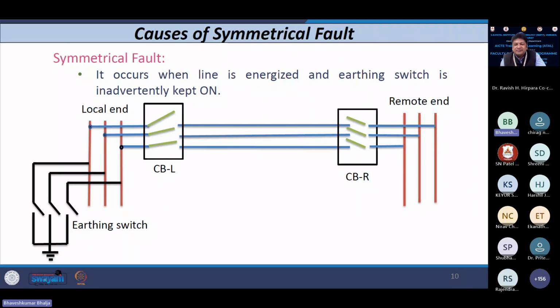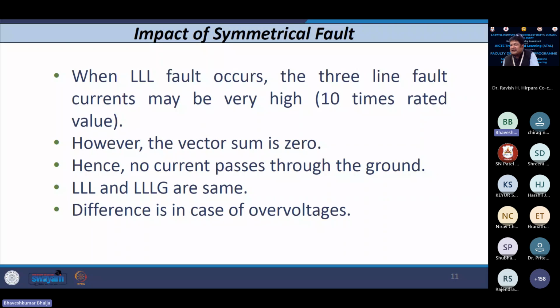When we need to carry out maintenance, and after that want to restore the supply, at that time the earthing switch comes into the picture. So if the earthing switch is on, let's say, on both sides, and you try to energize the transmission line, then a bolted three-phase short circuit occurs. However, as I said a minute ago, it is very rare, the rarest of the rare. The reason is there is a mechanical or electrical interlocking provided by the utility. So if you try to energize the line, assuming that the earthing switch is somehow on due to some reason, you are not allowed to energize the line. Such interlocking is already there.